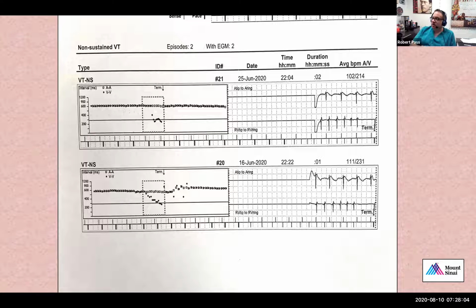Now, the only thing that this type of testing cannot do that we could do in the office is it can't check a threshold. And so that's another way to determine that the lead is stable. It's a very good way. And so that's one of the reasons that we like patients to come in, obviously, to be evaluated in the office. And so our general practice is to see patients twice a year in the office for a real visit, and for them to do these remote checks, which are going on automatically. And the other thing about these is if the patient is ever concerned about anything, they can command the device at home to do a download.